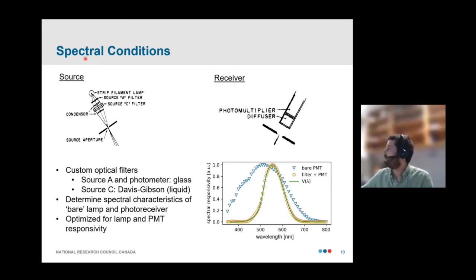The spectral conditions. So, what I mean by that is that we try to match our source spectral power distribution to CIE Illuminant C, and we try to match the spectral responsivity of our photometer to the V-Lambda function. So, we do that using several custom optical filters. In the source arm, we have a pair of filters, a glass filter, which actually acts to convert the emission from our lamp into something resembling source A. And then we have an additional Davis-Gibson liquid filter that's used to convert that into source C. This is a kind of classical optical device, the Davis-Gibson filter. It's actually a liquid filter. So, it consists of a pair of cuvettes, and you fill each cuvette with a suitable solution. And if you do this correctly, you'll get the correct transmittance spectrum that you're after.